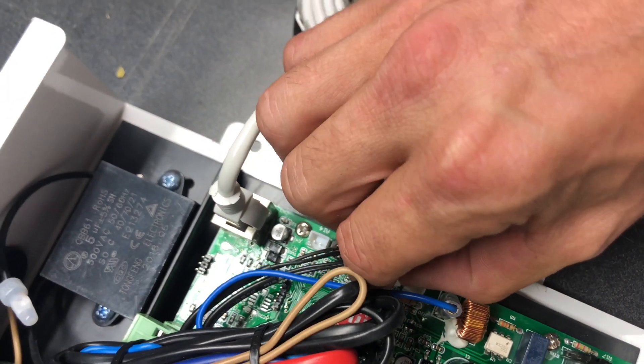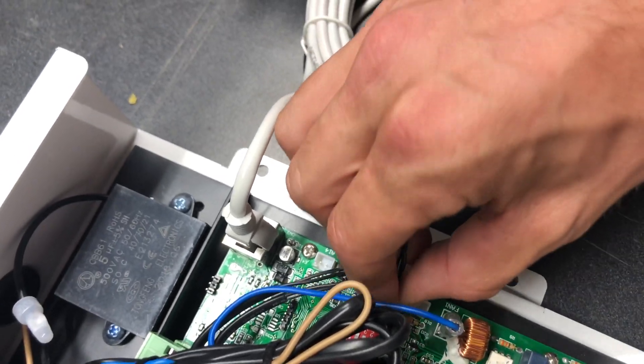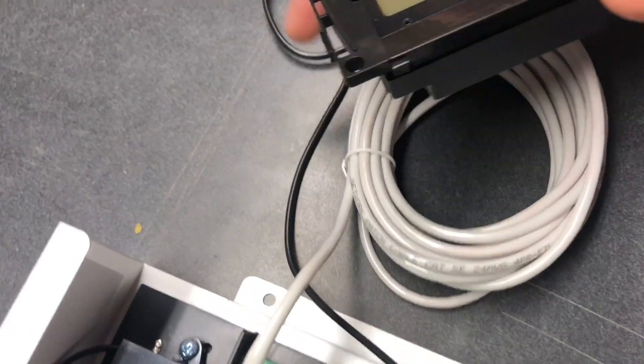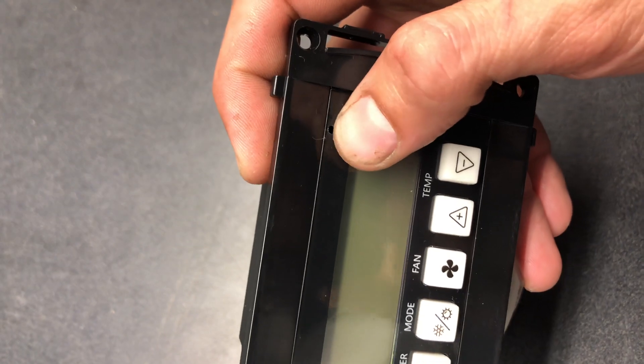The remote air sensor is not required, but it does give a more precise reading. If it's disconnected in this configuration, we are now reading off of the display out of this little slot right here. As soon as it's connected, this remote sensor has priority.